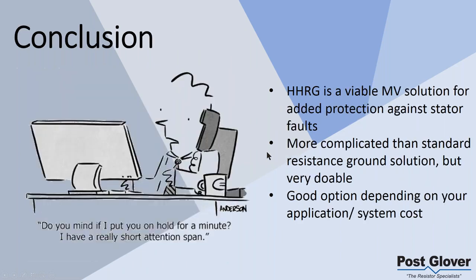Okay, so in conclusion of our introduction to hybrid high resistance ground, essentially it's a viable solution for medium voltage generators for protection against generator faults. It definitely is more complicated. You have more relaying, and the settings of the relays are more complex. I'm not a relay expert, but I've read a lot of papers. It's more complicated than your standard low resistance ground system, no question about it. However, it is doable, and it gives you the protection you need for the generator.